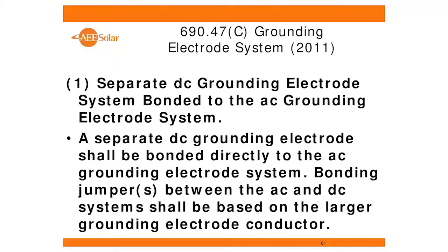That grounding electrode conductor is supposed to go to ground, and there are three options on how to do it. Option one is to go directly to the grounding electrode, and that grounding electrode could be any of a whole bunch of different things, including UFER grounds and ground rings and all that kind of stuff. Number one is where it goes to, let's say we drive a ground rod. So let's say we drive a ground rod at our inverter, and we take our grounding electrode conductor from the inverter to that grounding electrode.